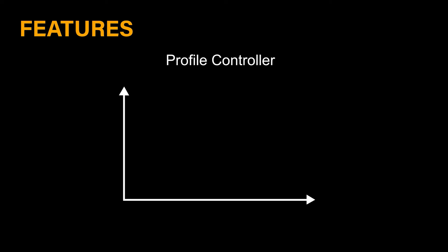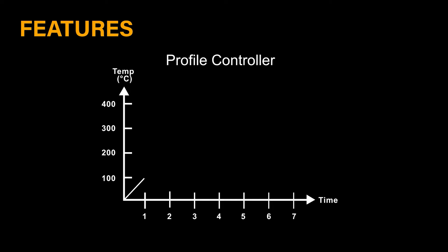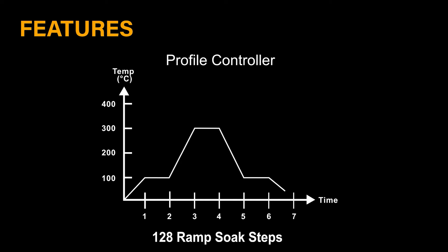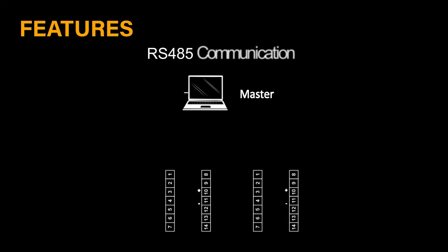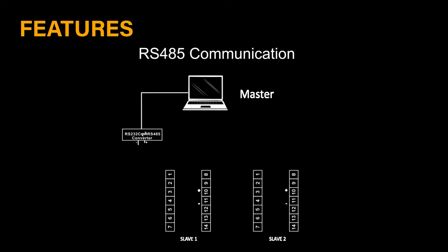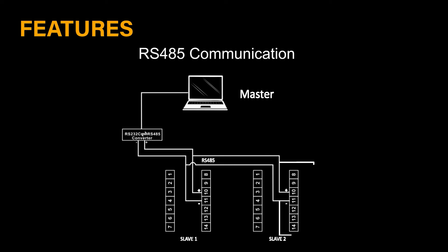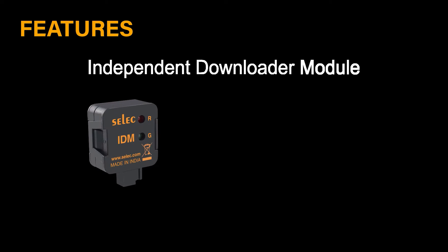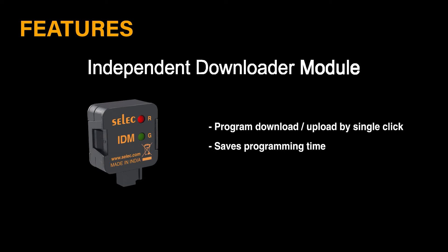For profile control, it has 8 programs with each program having 16 steps, giving a total of 128 steps for ramp soak. With RS-485 Modbus communication, the user can read and write various parameters in the PID controller remotely. An independent downloader module allows the user to program multiple controllers with ease, without the hassle of manually programming each product — with a simple click.